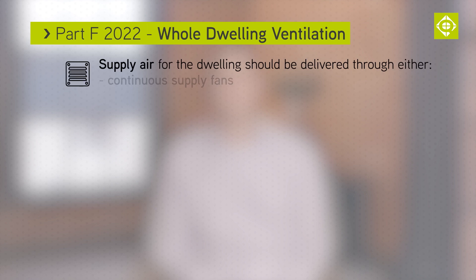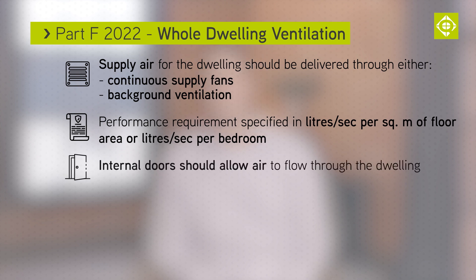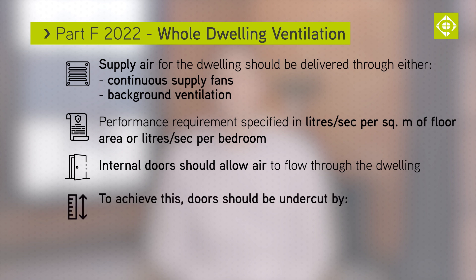Supply air for the dwelling should be delivered through either a continuous supply fan or background ventilation. The performance requirement is specified in litres per second per metre square of floor area, or litres per second per bedroom. Internal doors should also allow air to flow through the dwelling.